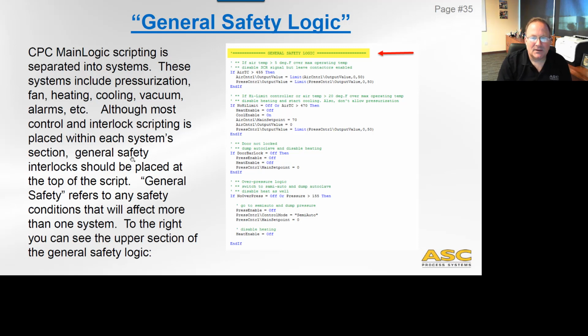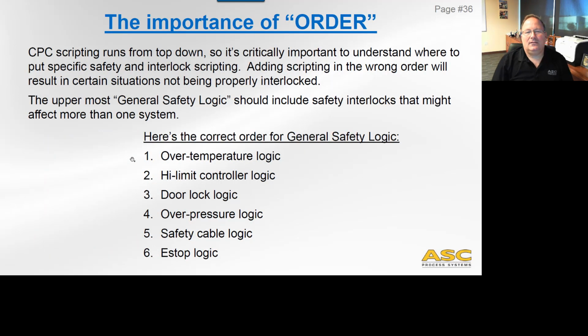This is kind of what you'll see there. Now, the order of scripting and how you put scripts in is very important in CPC, and I've seen lots of cases where control engineers do it incorrectly, put things in the wrong order, and the result is that the interlock isn't even working, okay? So the CPC scripting runs from top to bottom, so it's important to understand where to put specific safety and interlock scripting. Adding scripting in the wrong order will result in certain situations not being properly interlocked.